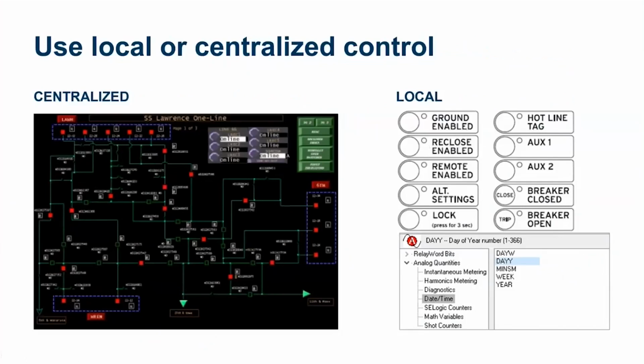So what is desirable in that case is to have a centralized control. So you can enable or disable reclosing on multiple reclosers at the same time. Ideally you should have communication to the reclosers so you can control them from a centralized controller. So for example, let's say you have a bunch of reclosers in a specific area and there is bad weather in that area, which might result in wildfires. In that case, you can consider disabling reclosing for all those reclosers in that area. So that's the advantage of having a centralized control over a local control.